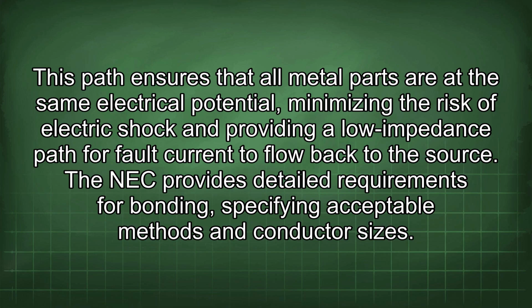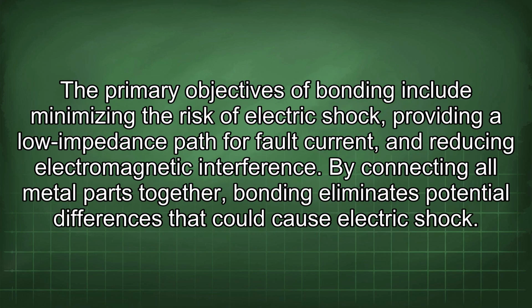This path ensures that all metal parts are at the same electrical potential, minimizing the risk of electric shock and providing a low impedance path for fault current to flow back to the source. The NEC provides detailed requirements for bonding, specifying acceptable methods and conductor sizes.